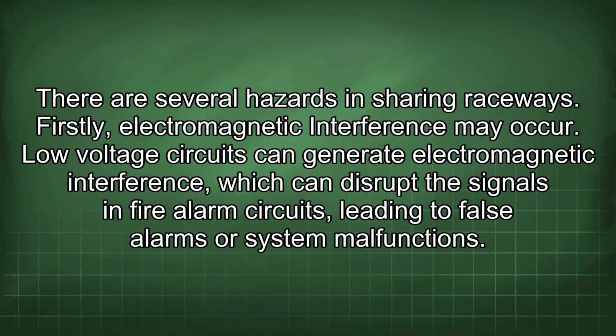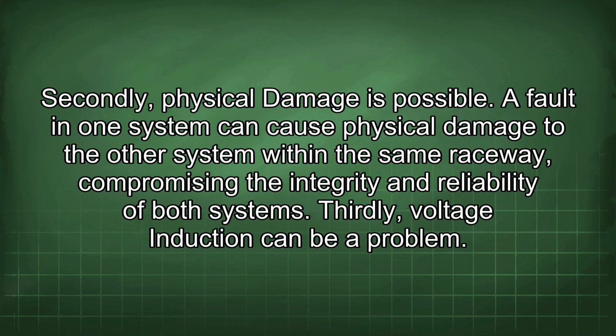Firstly, electromagnetic interference may occur. Low-voltage circuits can generate electromagnetic interference, which can disrupt the signals in fire alarm circuits, leading to false alarms or system malfunctions. Secondly, physical damage is possible. A fault in one system can cause physical damage to the other system within the same raceway, compromising the integrity and reliability of both systems.